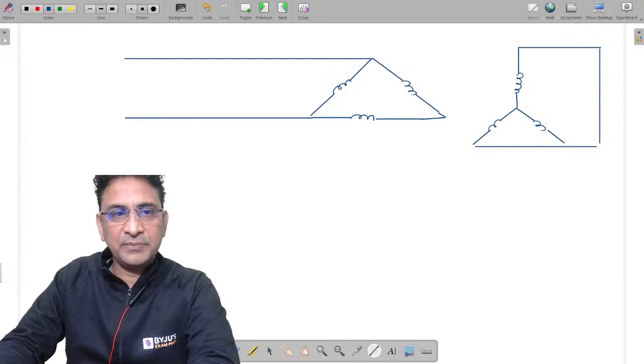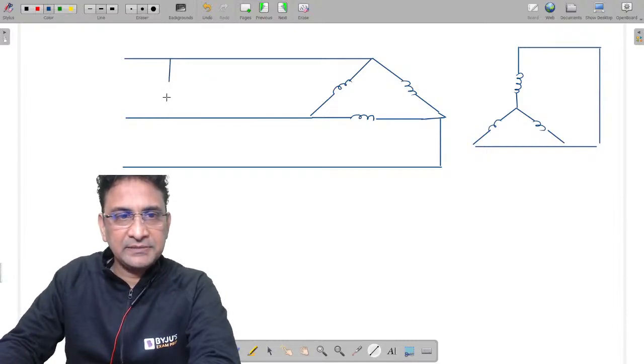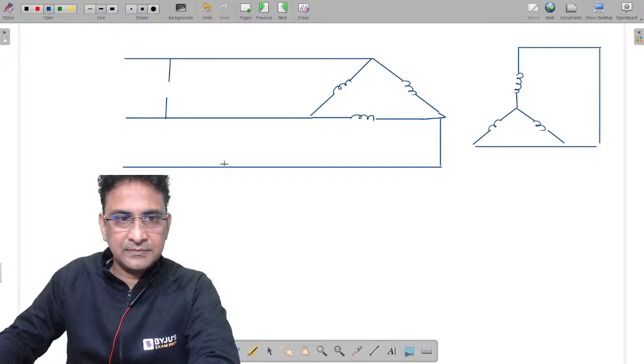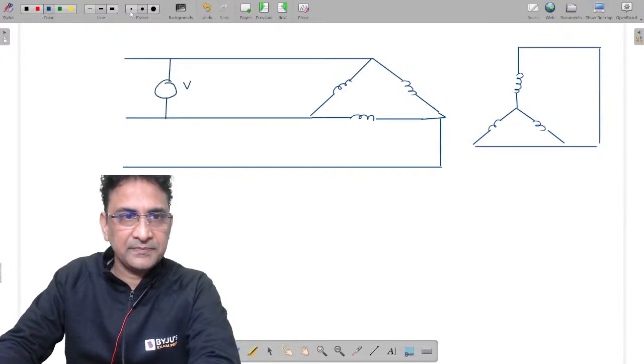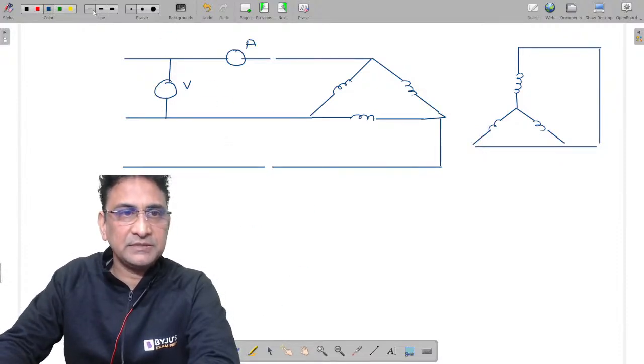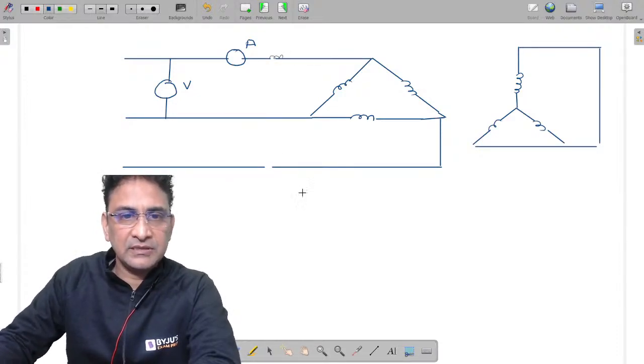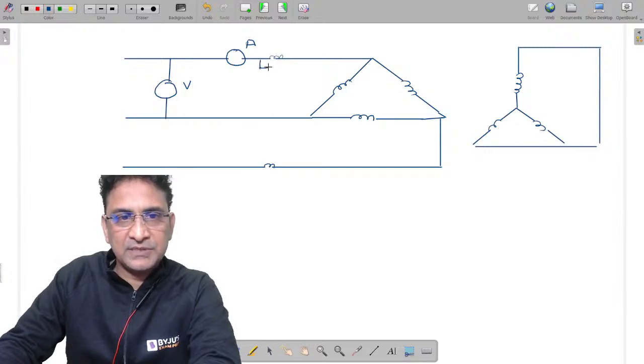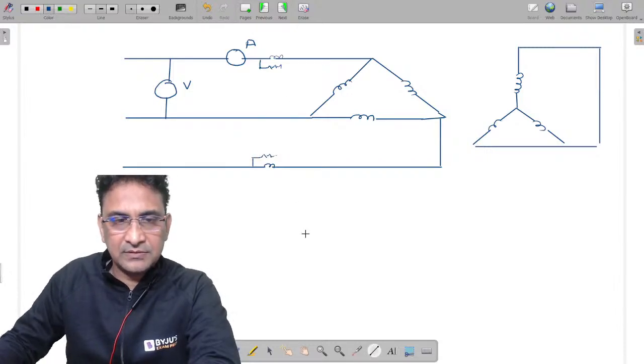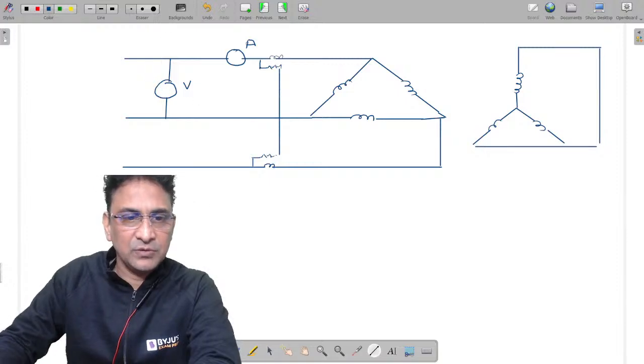So where do you connect the voltmeter, wattmeter and ammeter in the three-phase transformer? The voltmeter is connected between any two line terminals. This is the voltmeter, and the ammeter is connected here, and the wattmeter is connected. We connect either 2 wattmeters or 3 wattmeters, because the three-phase power can be measured using either 2 wattmeters or 3 wattmeters. The reading that is given is the sum of the 2 wattmeters or the 3 wattmeters. That means that is the overall wattmeter reading.